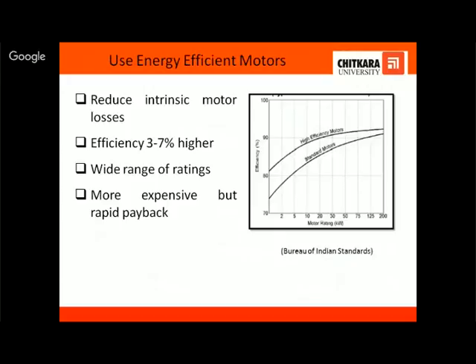Now the last is to make use of energy efficient motors. They are energy efficient three-phase induction motors. These motors have lower losses, and the efficiency is nearly 3 to 7% higher than the standard motors. There is a wide range of ratings. These motors are no doubt more expensive than the standard motors, but the payback period is very short. If we see the curves of the standard motor and high efficiency motors, we can see that the energy efficient motors are more efficient than the standard motors.